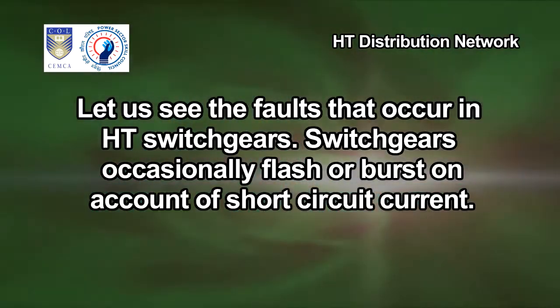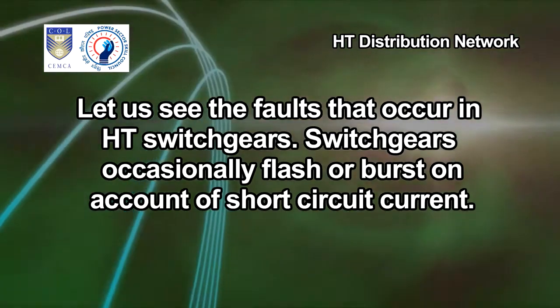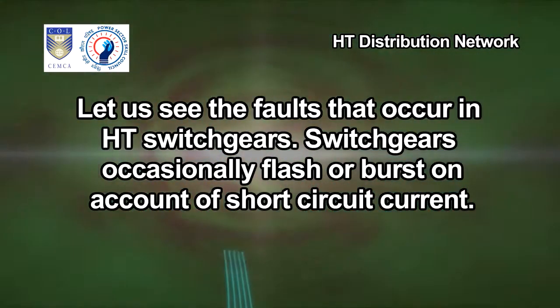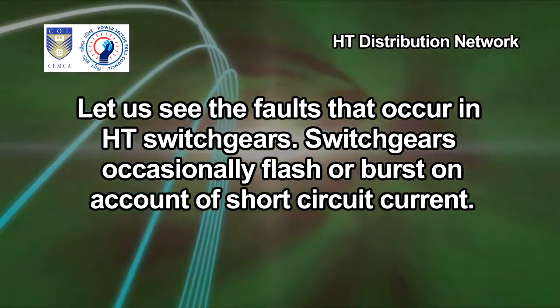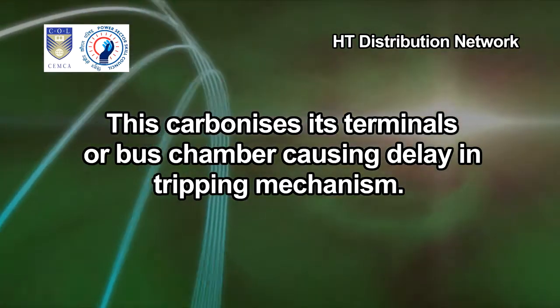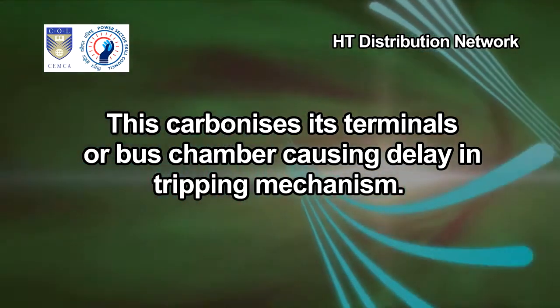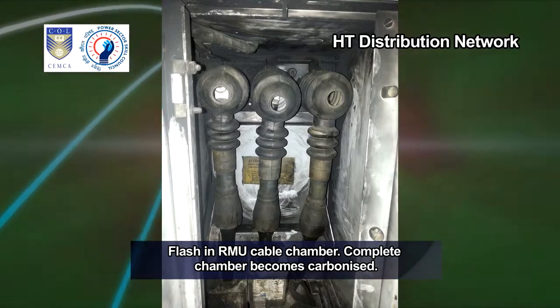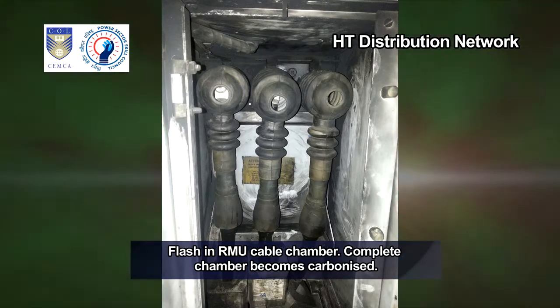Let us see the faults that occur in HT switch gears. Switch gears occasionally flash or burst on account of short circuit current. These carbonizes its terminals or bus chamber, causing delay in tripping mechanism. Flash in RMU cable chamber, complete chamber becomes carbonized.